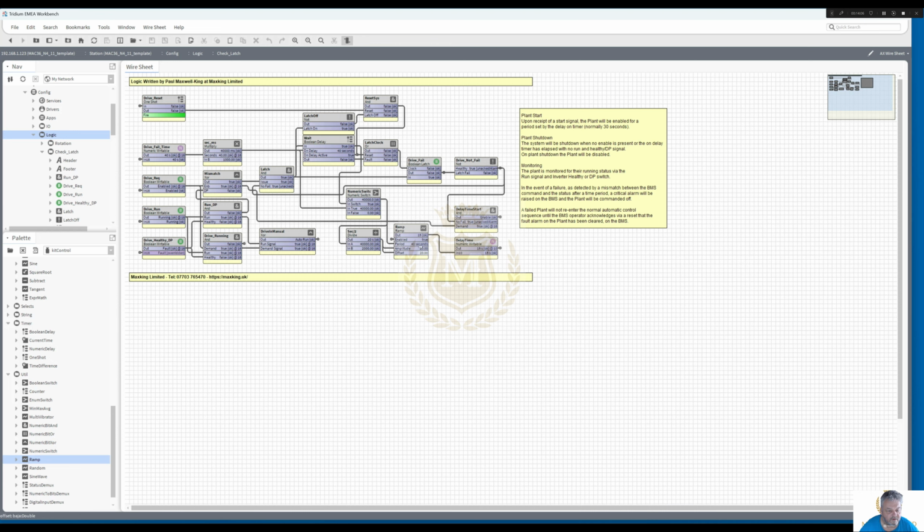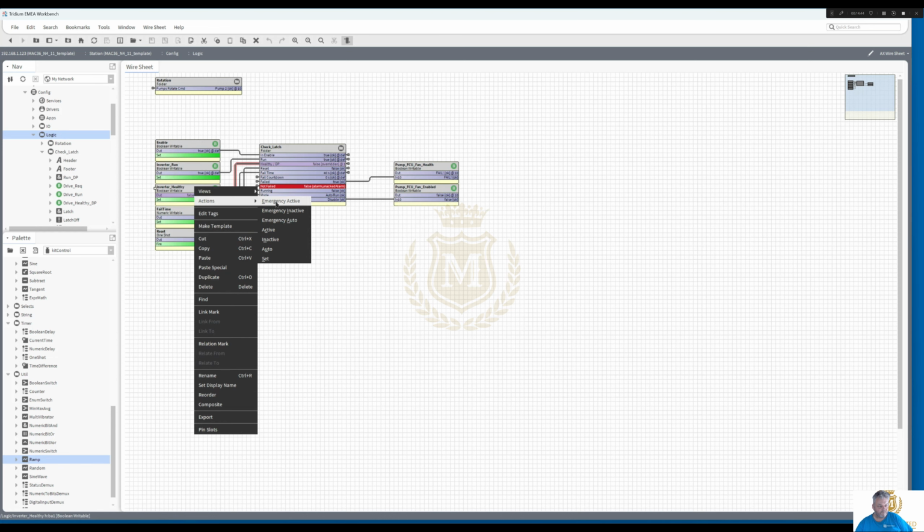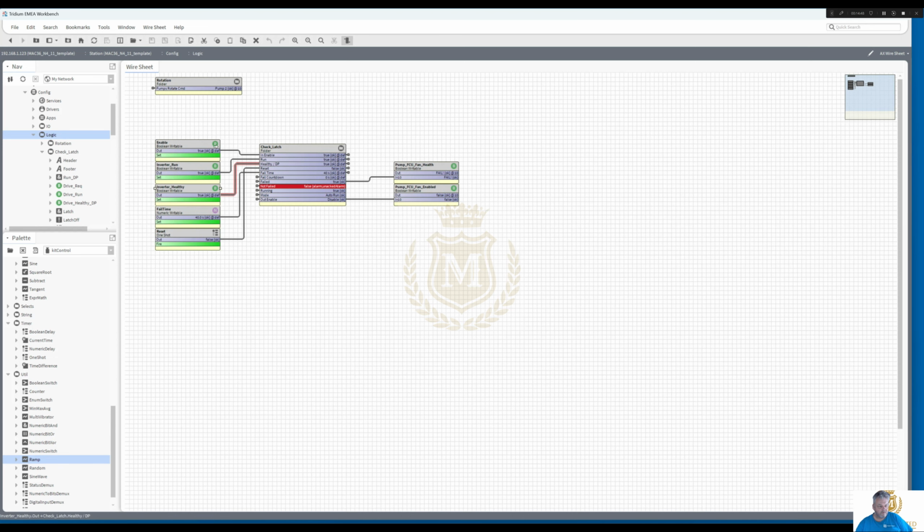And after 40 seconds, the delay output will change from false to true, which goes into this OR. So this would be true, this would be true, and then of course it will capture that true signal, which it has done. So nothing can happen now with that inverter without doing a reset, even if you make it healthy. So let's make it all healthy again. We're asking for it to run. Inverter is saying running. Inverter is healthy. We've got our fail time there, but we've still got our output and we've still got our fail until we do a reset.